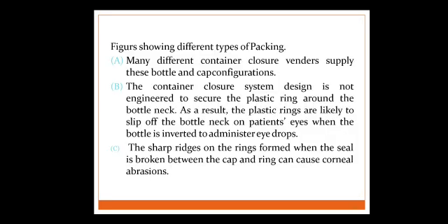The container closure system design is not engineered to secure the plastic ring around the bottleneck. As a result, the plastic rings are likely to slip off the bottleneck onto patient eyes when the bottle is inverted to administer eye drops.